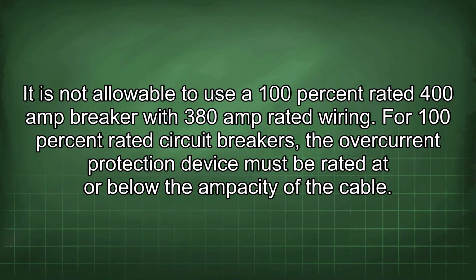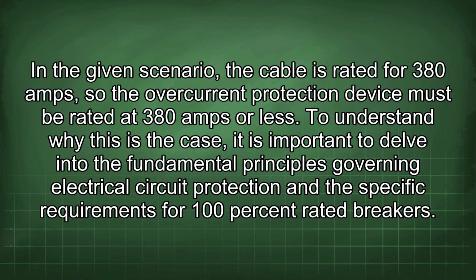It is not allowable to use a 100% rated 400 amp breaker with 380 amp rated wiring. For 100% rated circuit breakers, the overcurrent protection device must be rated at or below the ampacity of the cable. In the given scenario, the cable is rated for 380 amps, so the overcurrent protection device must be rated at 380 amps or less. To understand why this is the case, it is important to delve into the fundamental principles governing electrical circuit protection and the specific requirements for 100% rated breakers.